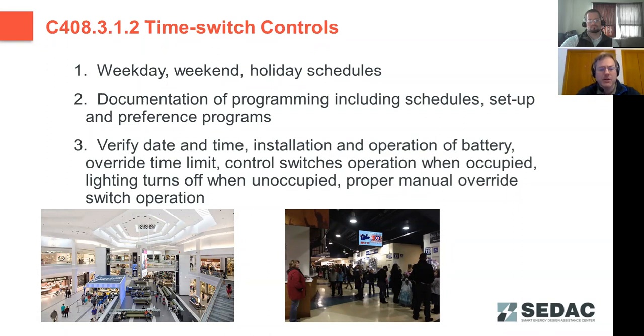the building management can reinstall the program appropriately. So just a lot of different verifications here, making sure that the override time is limited to either 2 or 10 hours, depending on the space type. Control switch operations, as well as verifying that the battery or other backup power supply is functioning.